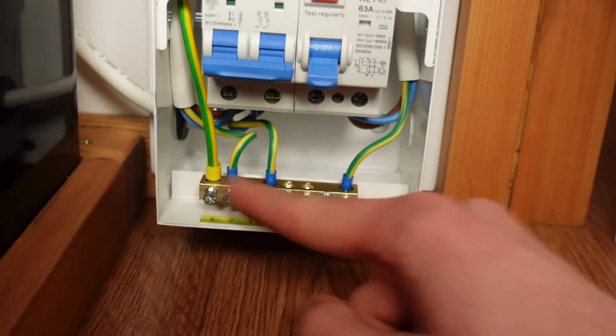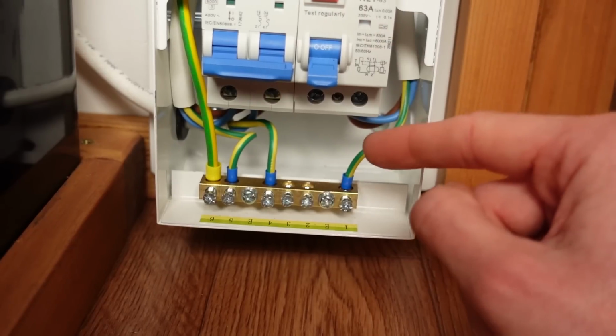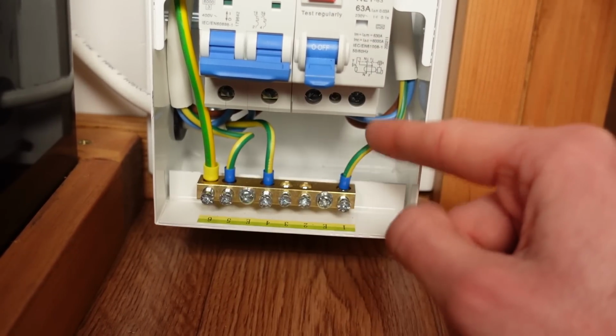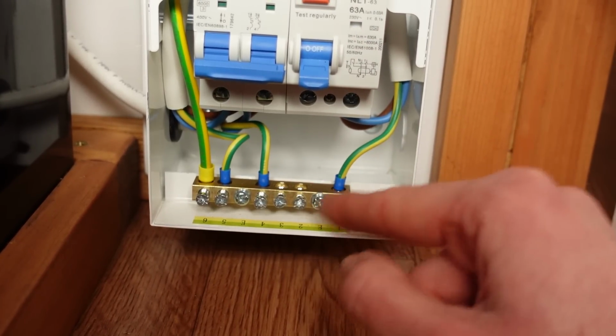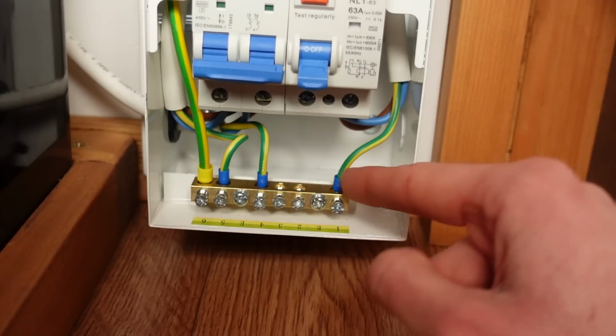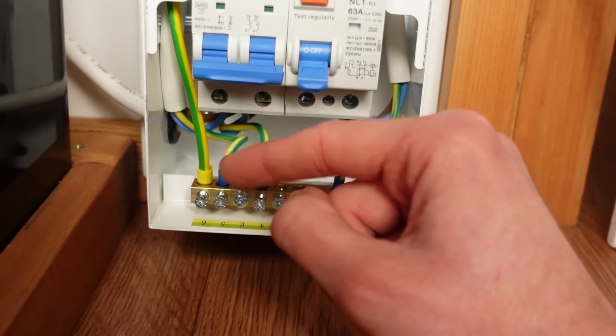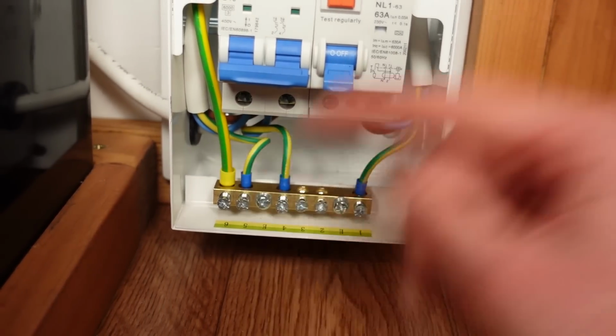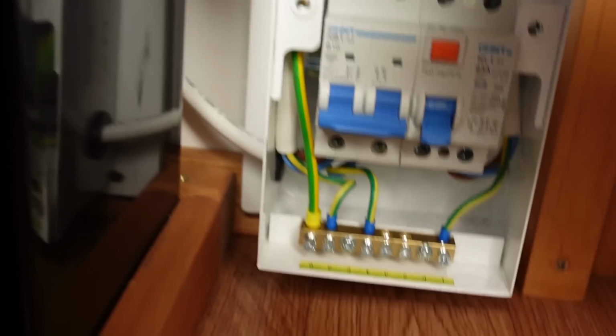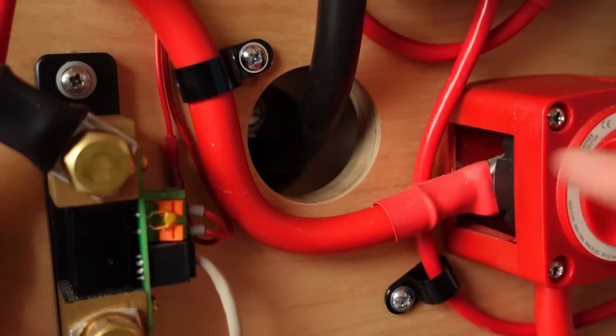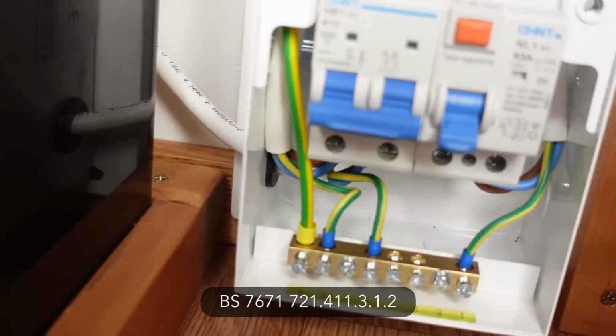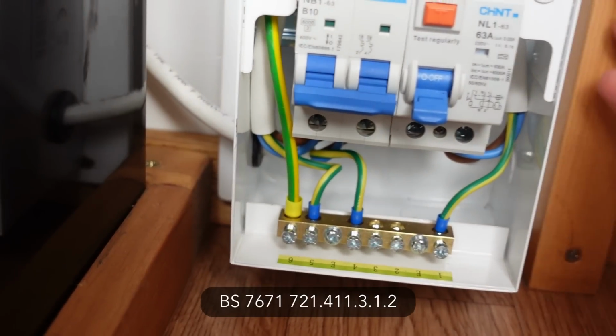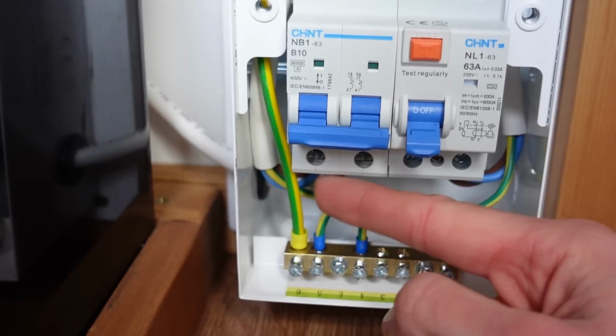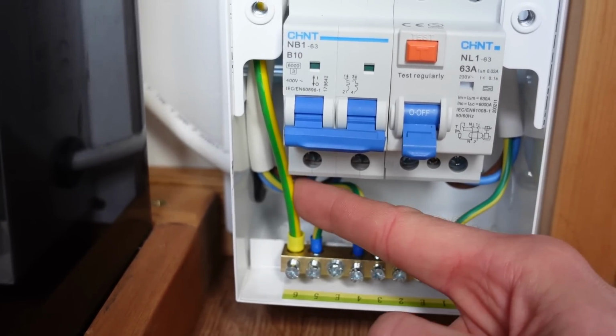So we've just added some ferrules on here to tidy up the wires in the consumer unit, because we're using fine stranded cables, so without a ferrule, when you screw down this screw onto them, it sort of crushes the wires a little bit. We've also added a separate earth wire just for the consumer unit, which goes to the chassis on our ground point. The reason for that is to satisfy one of the British standards, which says the chassis needs to be bonded to the main earthing terminal. So that's a 6mm tri-rated flexible earth wire.